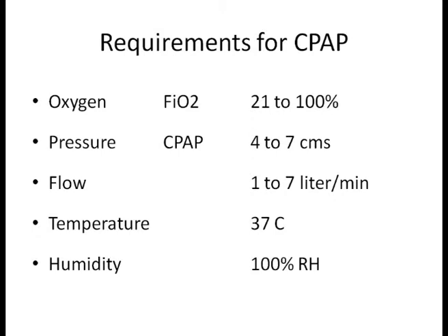Apart from pressure and oxygen, we also need to warm and humidify the gases which are going to be delivered to the baby's nose. And the temperature of the gas when it goes to the baby should be at a temperature of 37 degrees Celsius with a relative humidity of 100%.